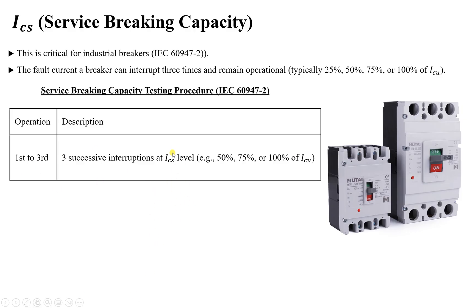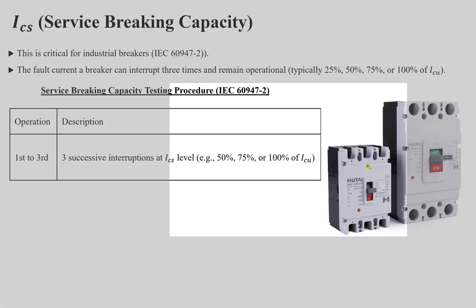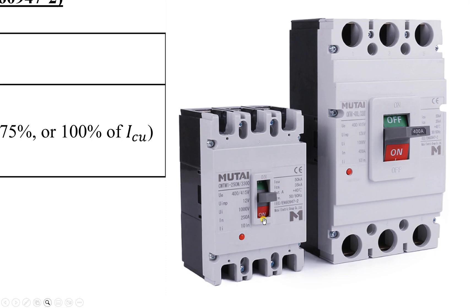After those faults, they also test dielectric strength by applying an overvoltage. Looking at this breaker, you can see ICU is 50 kilo-ampere — the maximum fault current it can interrupt without damage, at most once. ICS is 35 kilo-ampere, which is less than ICU, and represents the service breaking capacity. This means the breaker can interrupt 35 kilo-ampere several times, at least three times according to the testing procedure.